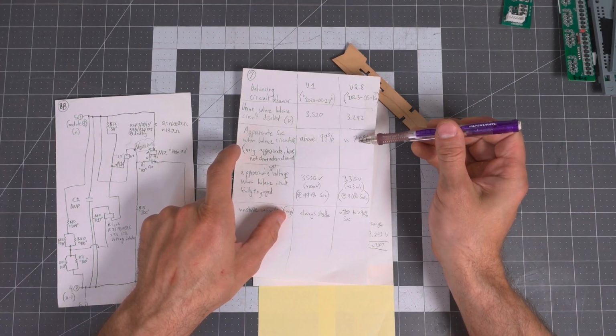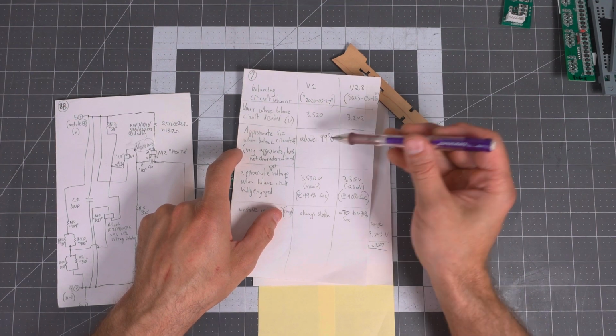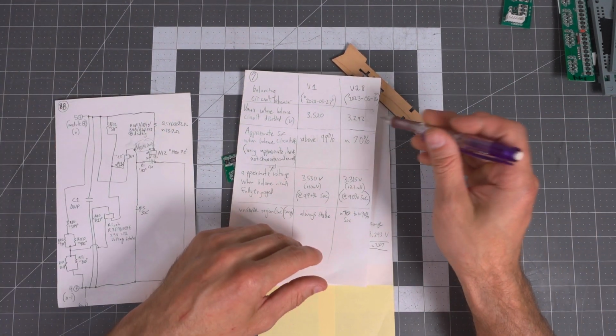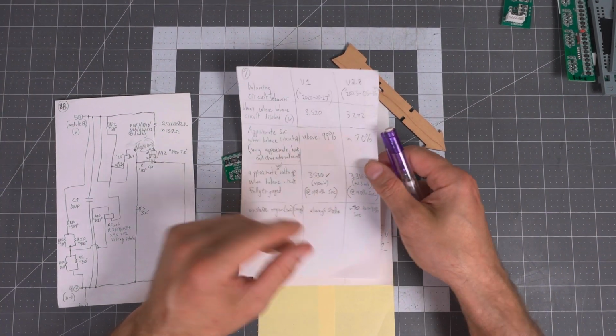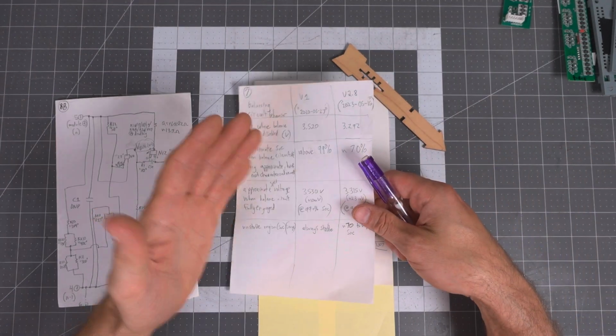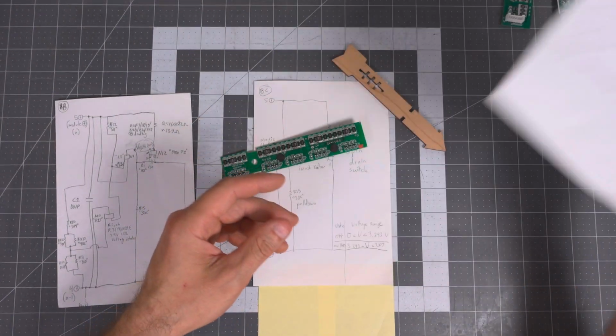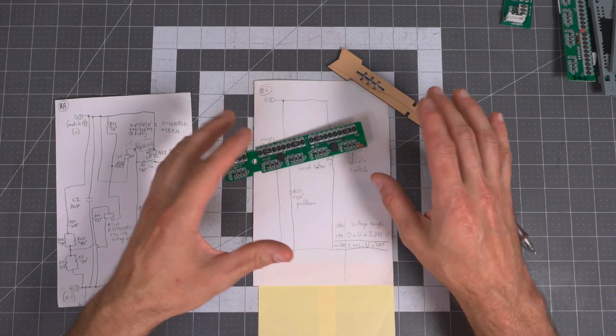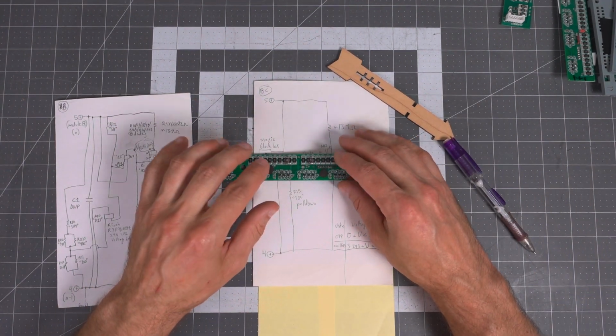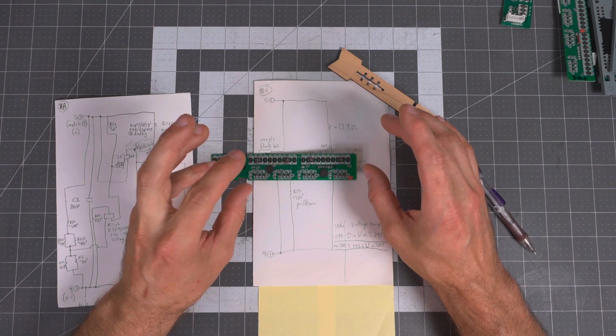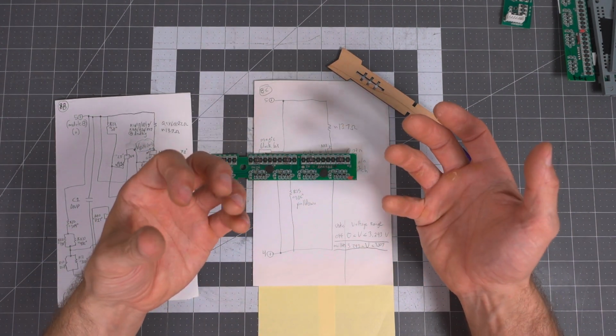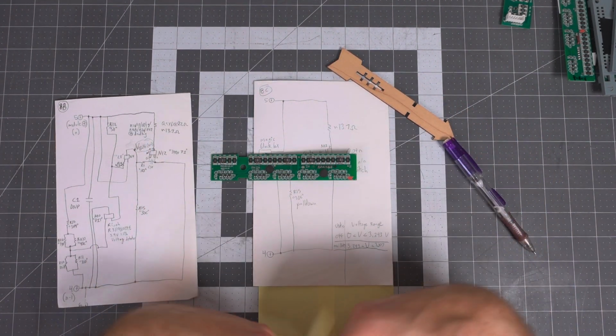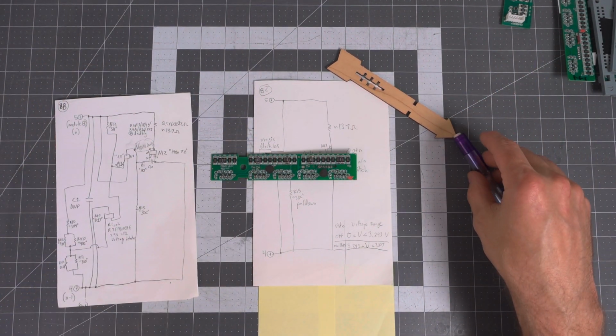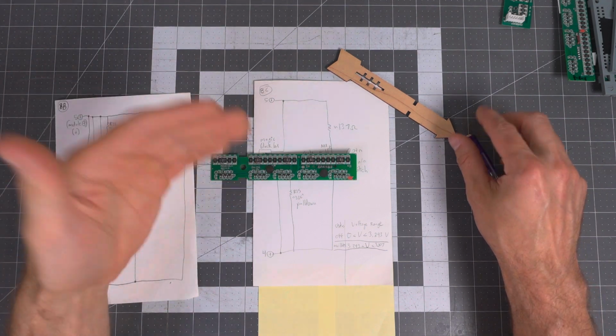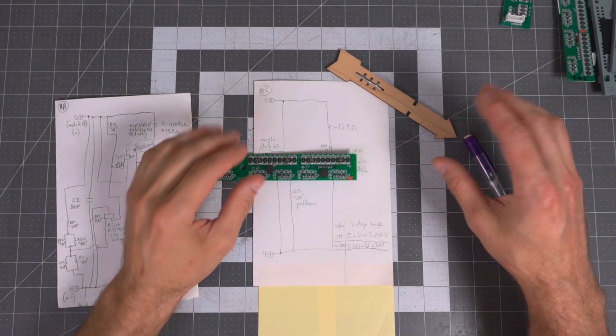Then a disconnected connector could cause that other module to stay fully charged, where the other ones are always getting bled down to 70%. Now you have a pack imbalance that's actually introduced by the thing that's trying to balance the pack, because the connector wasn't plugged in. That's the only case where the unplugged connector would cause that specific module to overcharge, because the other ones are getting discharged to 70% and this one is staying at 80 or 90 percent or whatever.